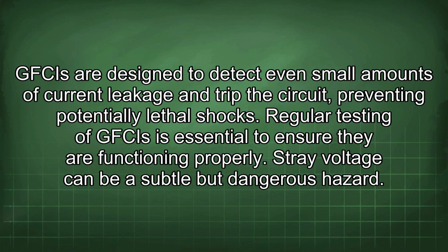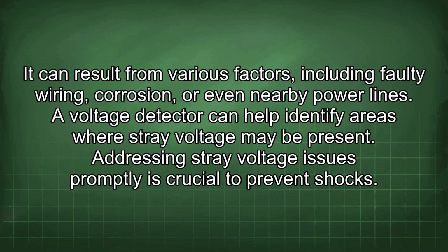Stray voltage can be a subtle but dangerous hazard. It can result from various factors, including faulty wiring, corrosion, or even nearby power lines. A voltage detector can help identify areas where stray voltage may be present. Addressing stray voltage issues promptly is crucial to prevent shocks.